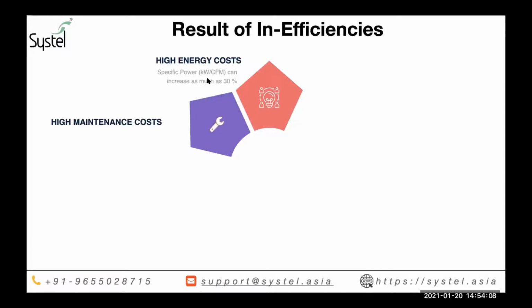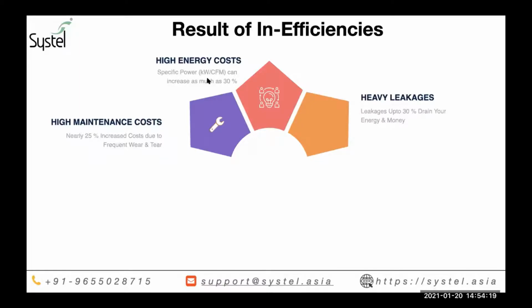The first inefficiency that you're going to experience is higher energy cost, and usually the specific power can be as much as 30% higher if there is no proper monitoring on the supply side of the system. It could also lead to high maintenance cost due to higher operational hours of the compressors and allied equipment. And higher system pressure could also lead to leakages, and leakage levels of 20 to 30% are very, very common that we see in the industries here.